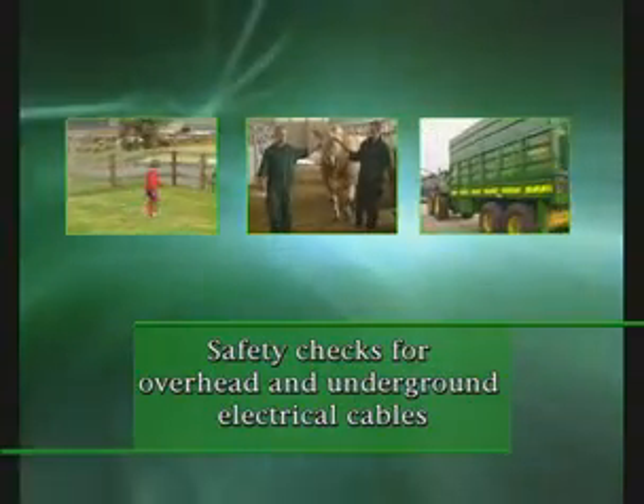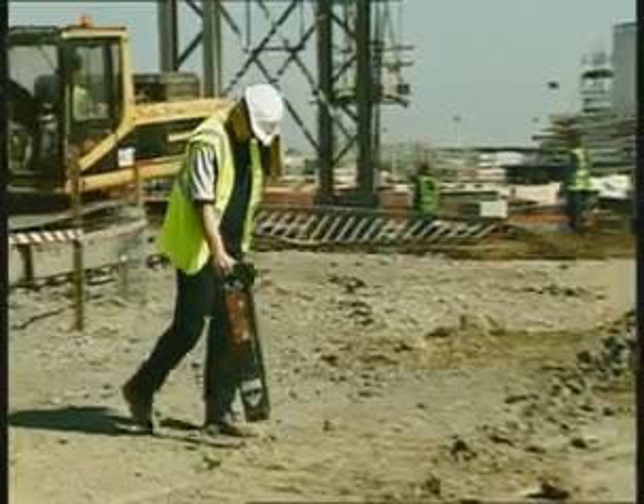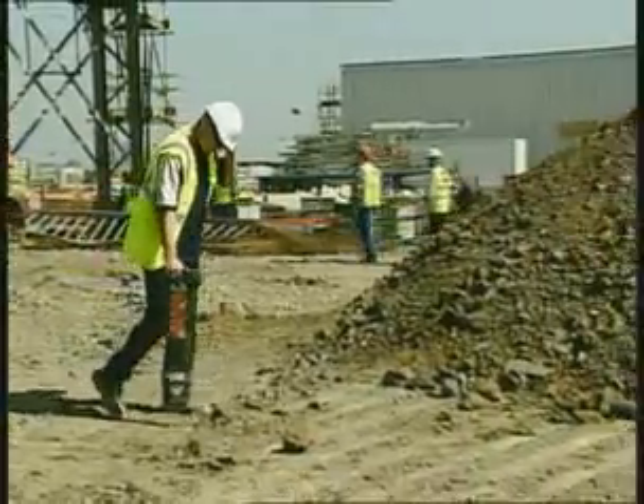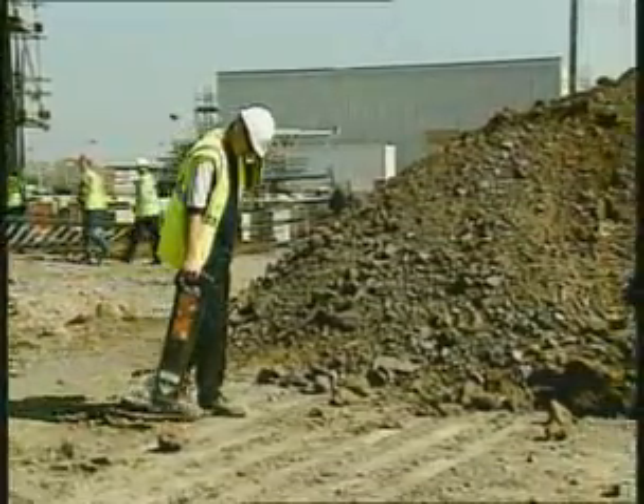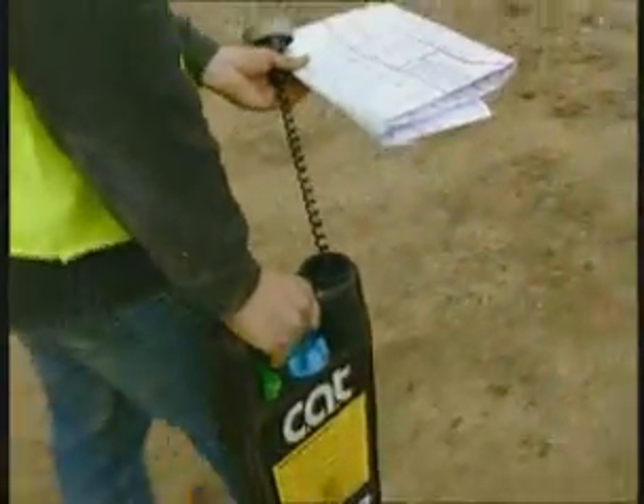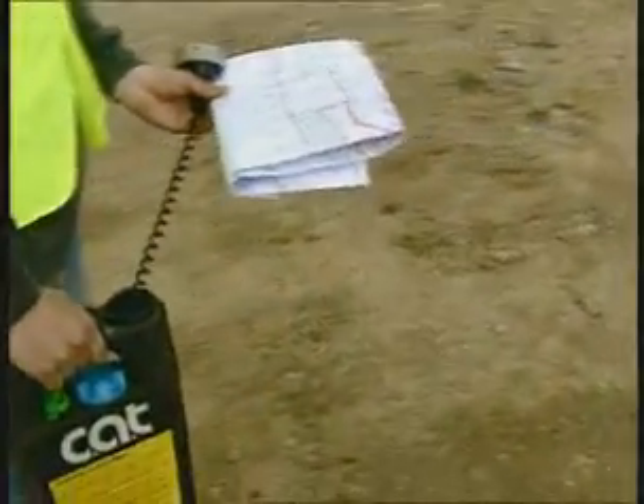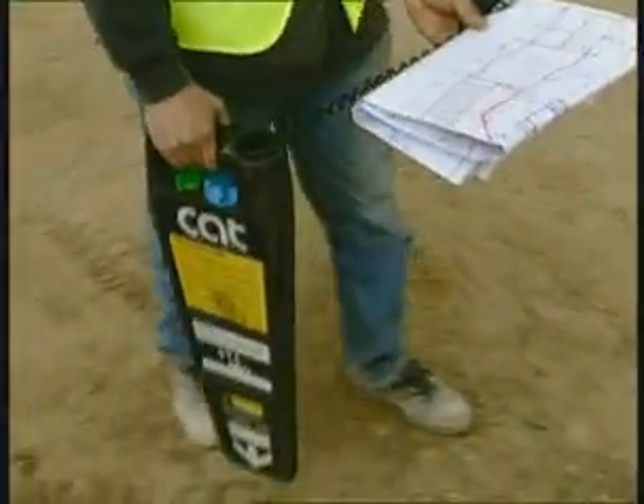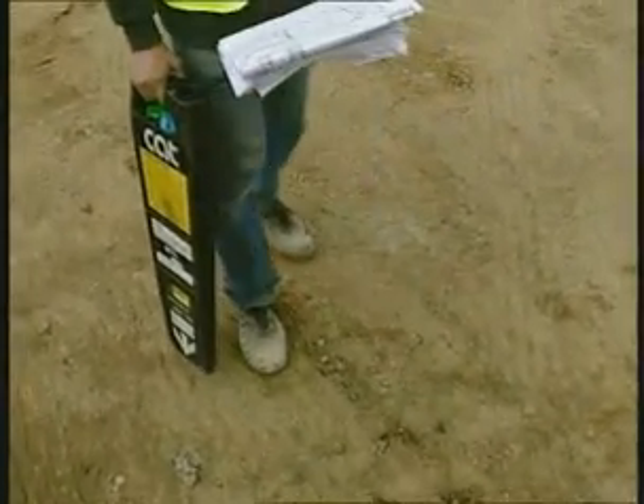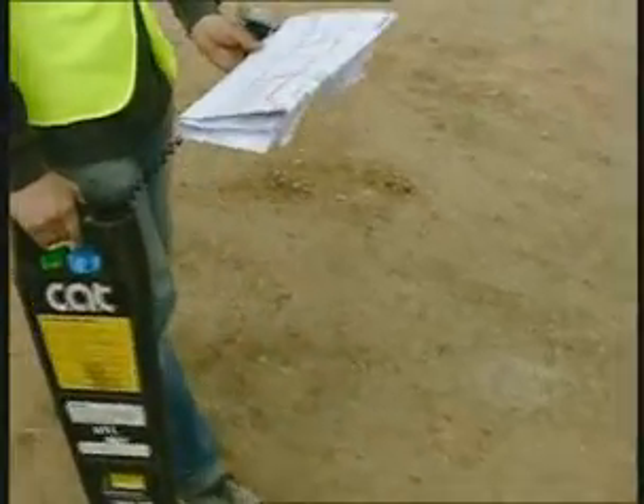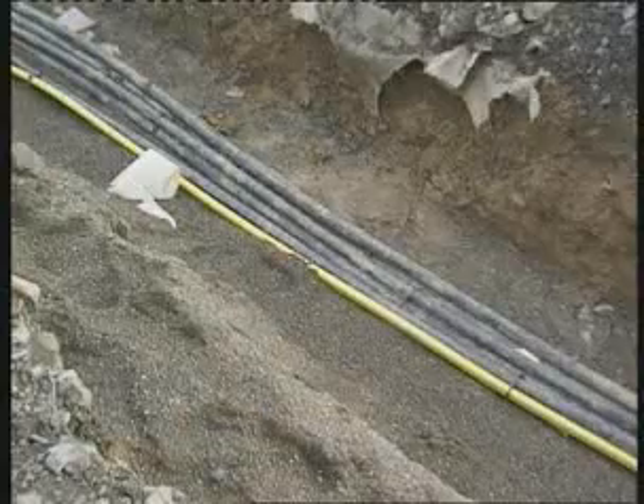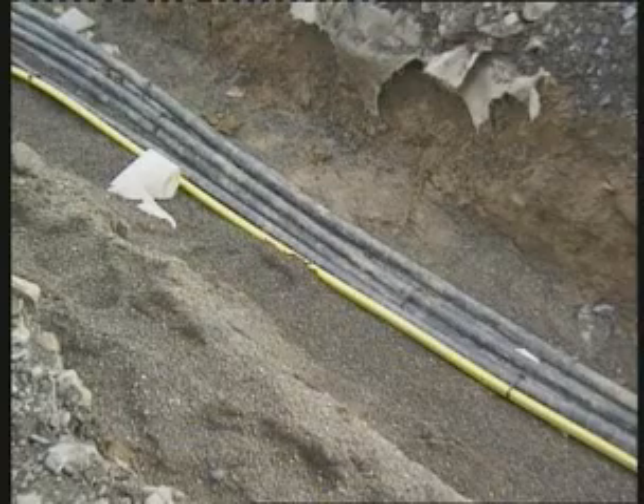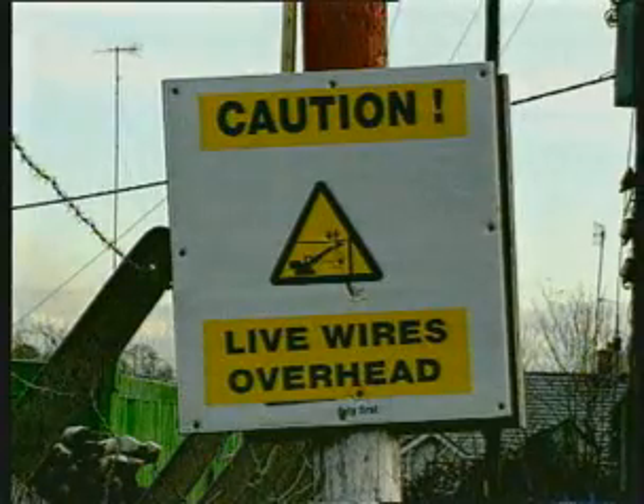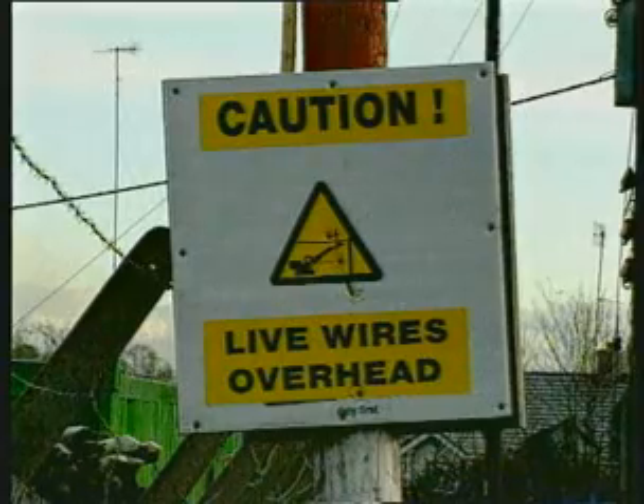Safety checks for overhead and underground electrical cables. Are underground cables buried at least 750 millimetres or 2 foot 6 inches below the surface and mechanically protected where necessary? Where underground cables emerge from the ground and are fixed to walls and buildings, are they mechanically protected for 1.25 metres or 4 foot 6 inches above ground level? Are all overhead electric cables at least 6 metres or 20 foot above ground level, especially over roads or gateways used by high loads or machines?